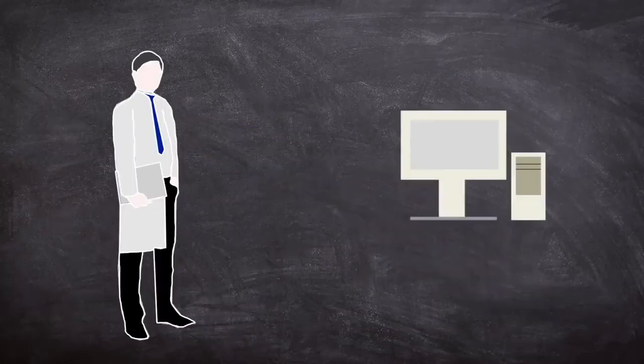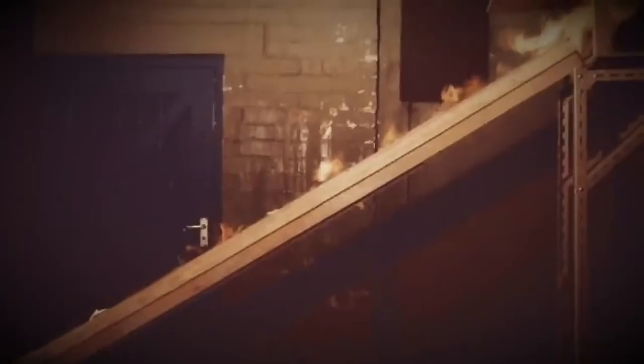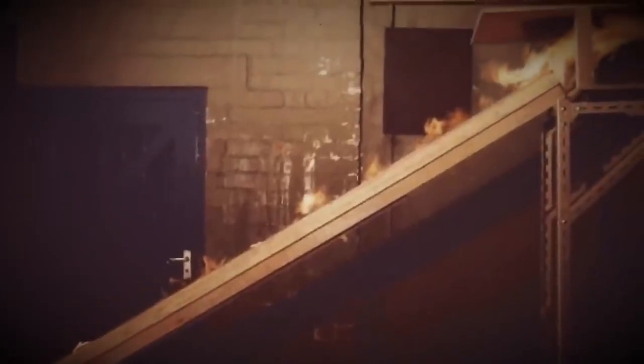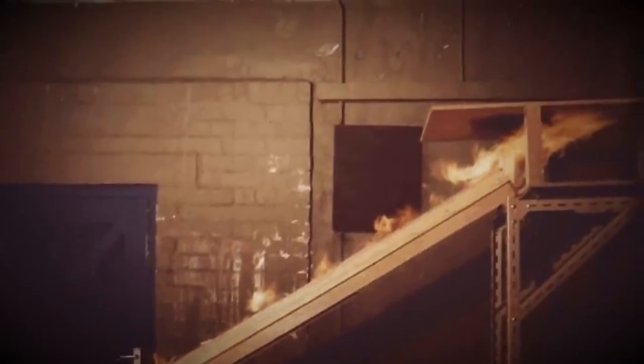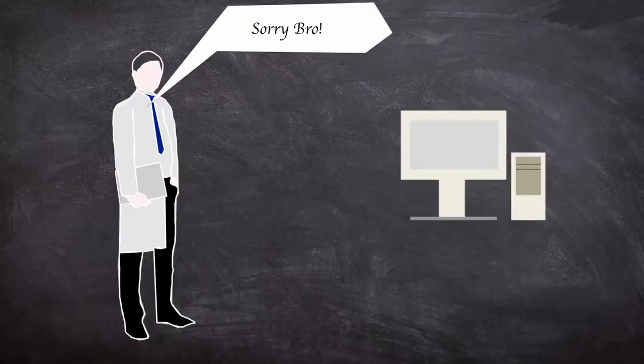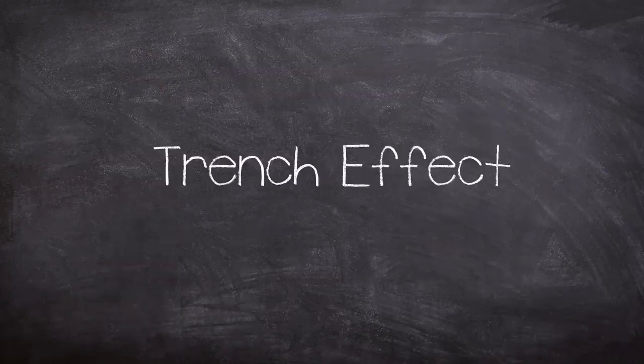The health and safety executive sceptical of the computer results made a scale model of the escalators and ticket hall and lo and behold in the next experiment the fire followed the exact same characteristics of the computer simulation. The now newly discovered phenomenon was called the trench effect and was the ultimate reason for the extreme flashover.